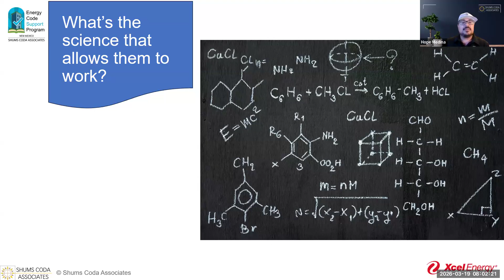So, for example, let's take a look at a furnace. 100,000 BTUs of input - that's a really common size, or a really simple math size, for a furnace to look at. And we're going to say it's 90% efficient, so an AFUE of 90%, a relatively high efficiency furnace. What that really means is that we get 90,000 BTUs of output, and 10,000 BTUs are going to be lost to imperfect combustion in that system. That's going to be system waste, effectively - heating the heat exchanger, the temperature rise differential, the things that we can't get full combustion and full heat out of.